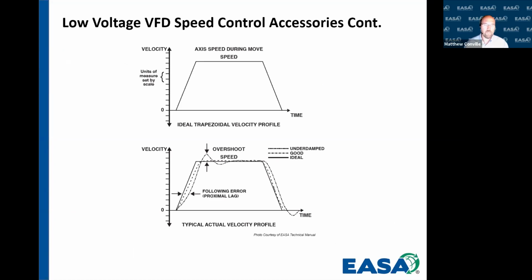So when I talked a little bit about speed control, here's an example of a speed profile or a preset that we might want. So in this operation or process, we may want to accelerate, maintain a certain speed, and then decelerate over time. When we don't use an encoder or a resolver, it's very possible that our speed profile might look like this, where here's our preset and here's what we actually have. We've got large deviations to get to the appropriate speed over time. And then as we get to our speed set point, we'll actually overshoot or overspeed.